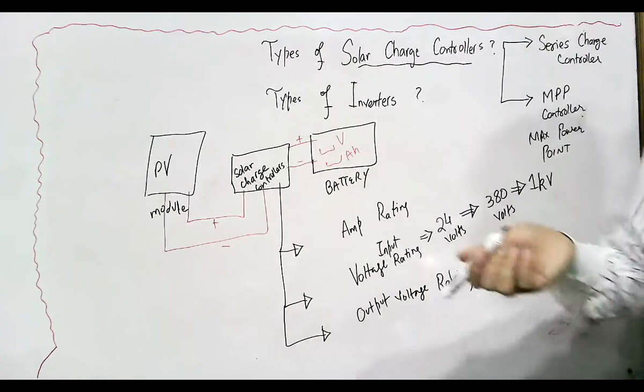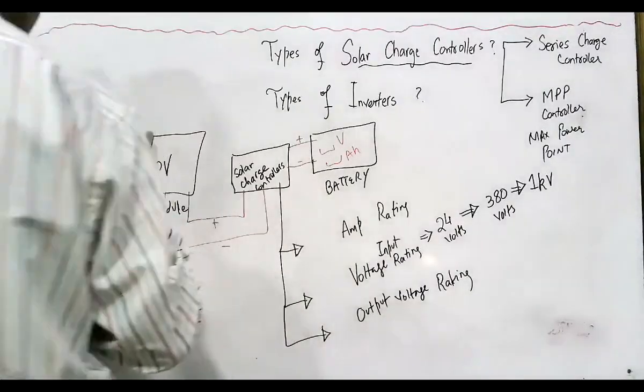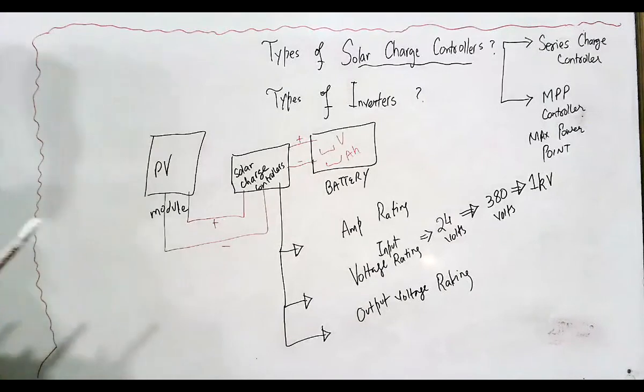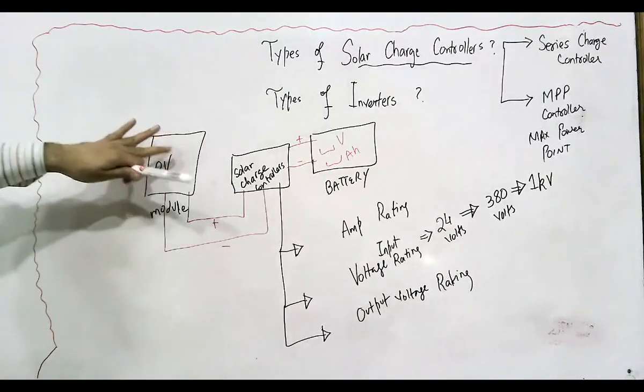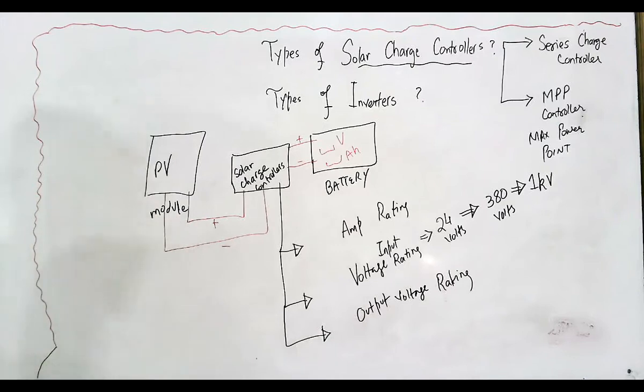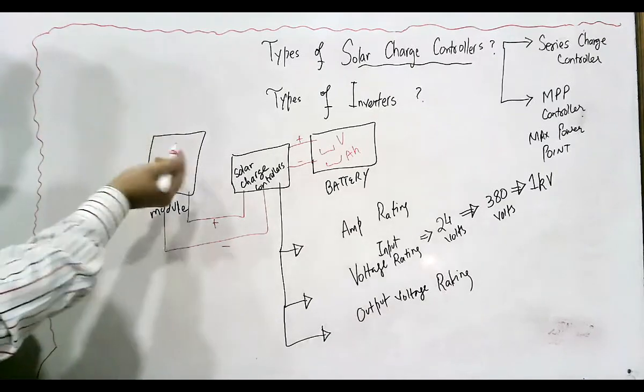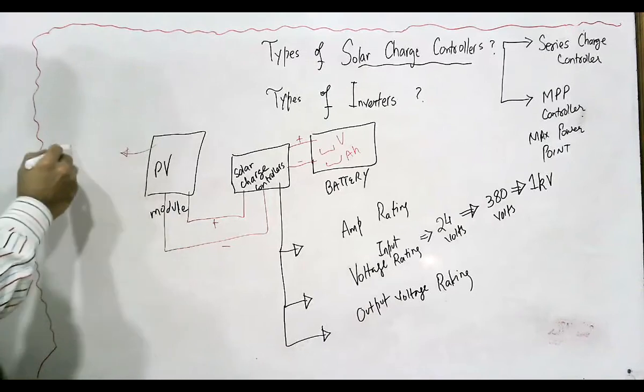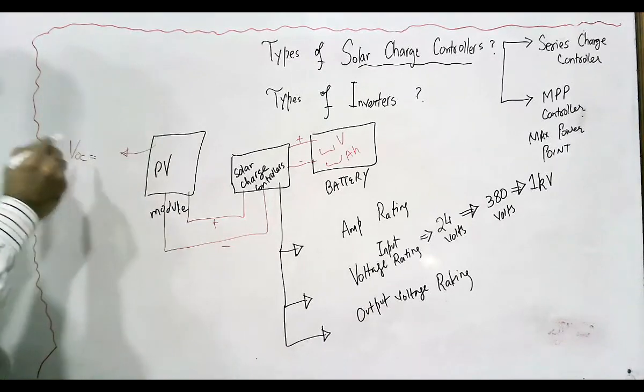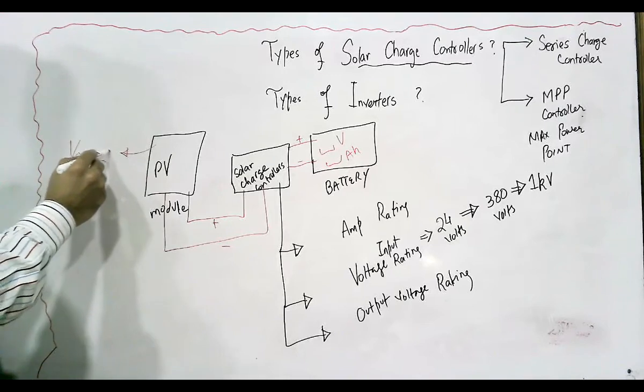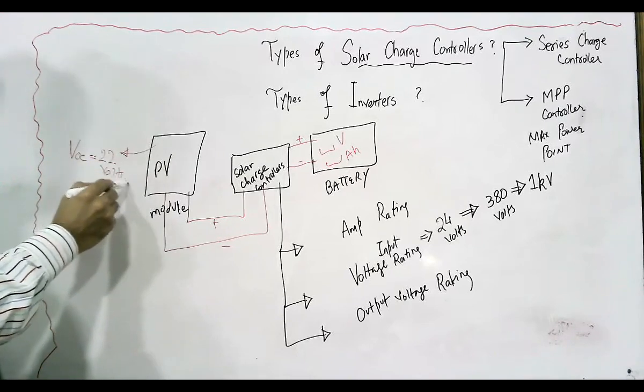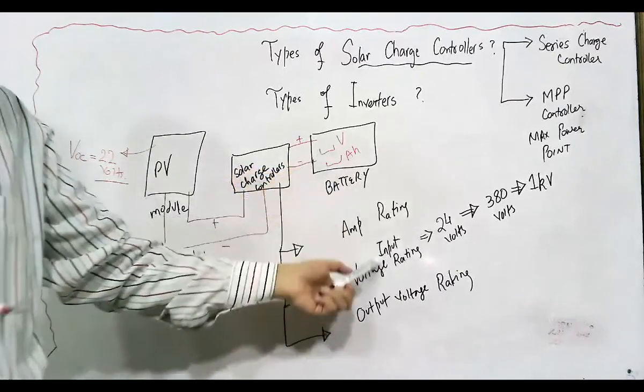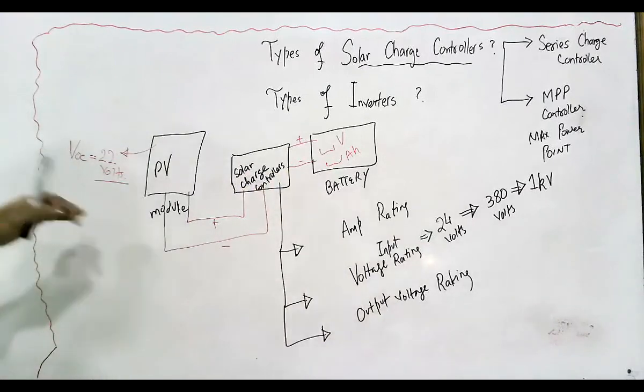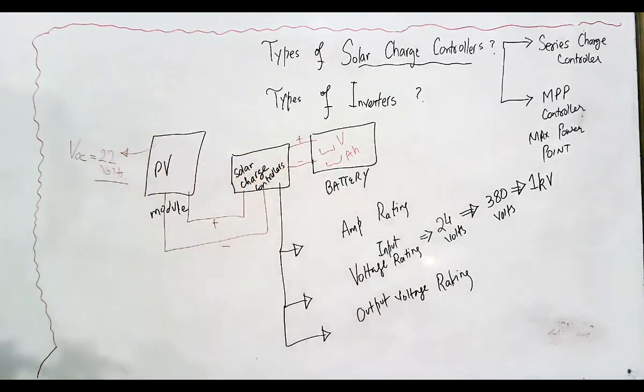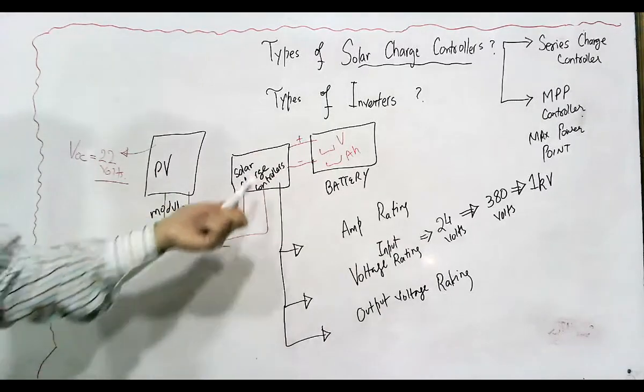As I told you, if this is a PV module, there is a nameplate or rating sheet attached, or it comes along with the PV array or module. Let's say your PV module's open circuit voltage is mentioned as around 22 volts. Then the battery charger you choose must have an input voltage of 24 volts, or higher. This is the general rule for deciding its rating.